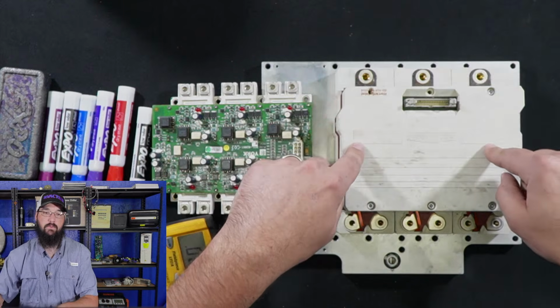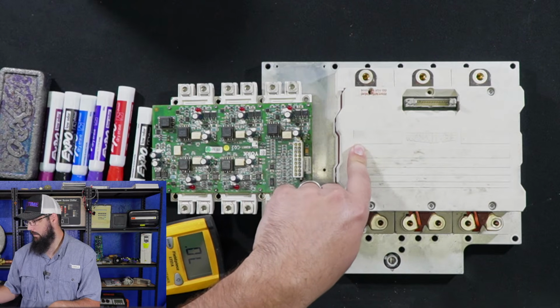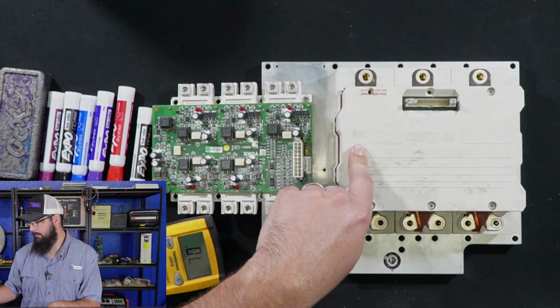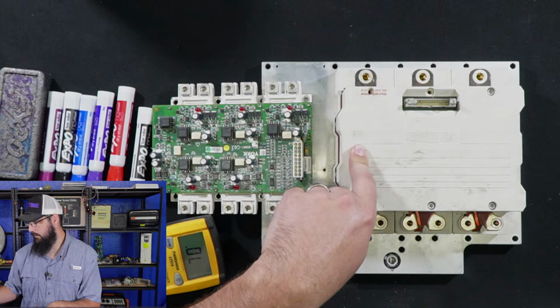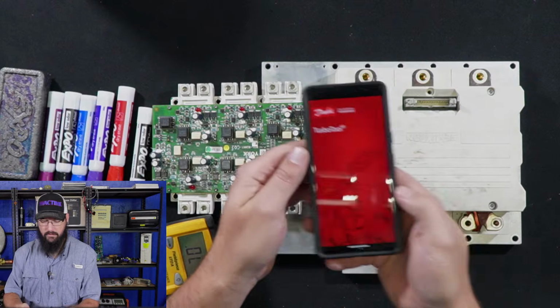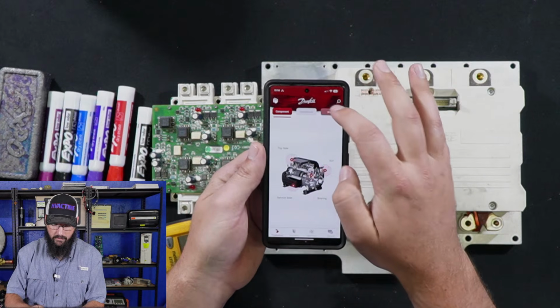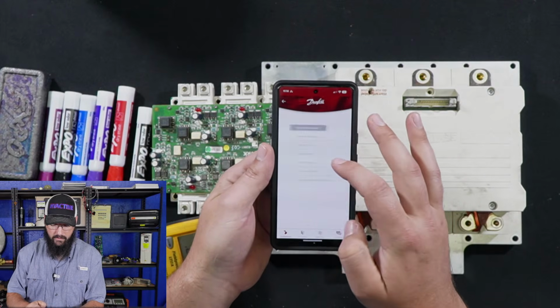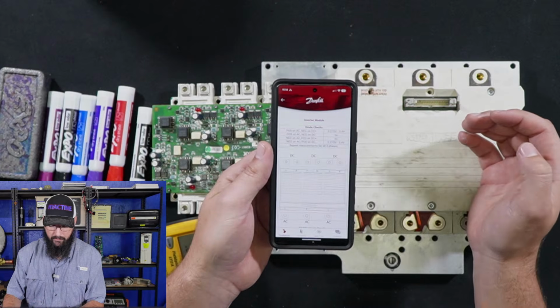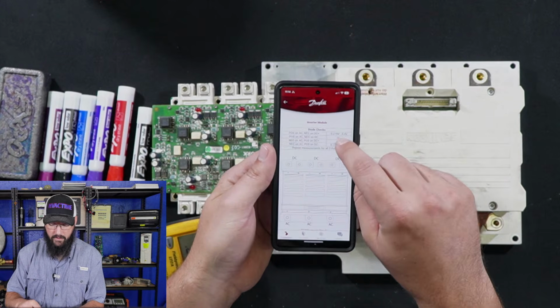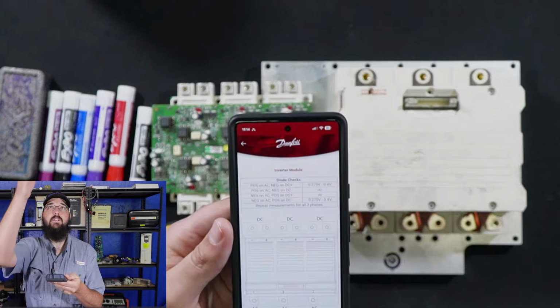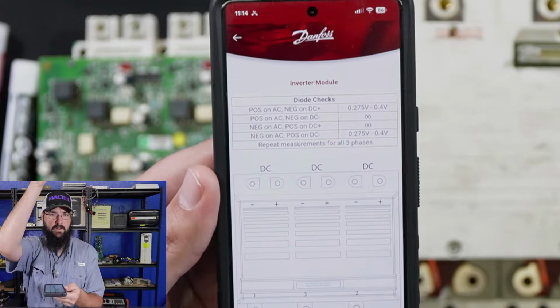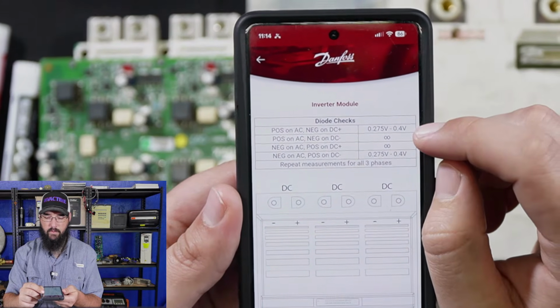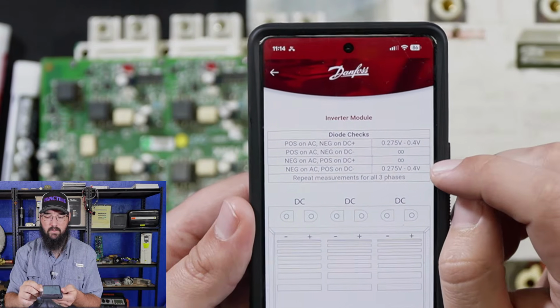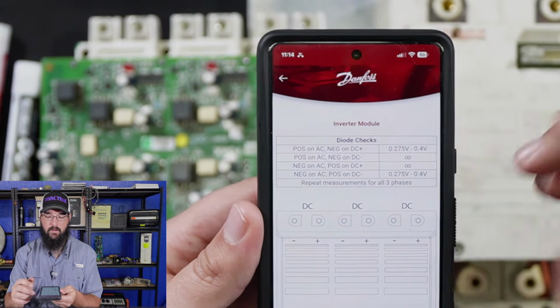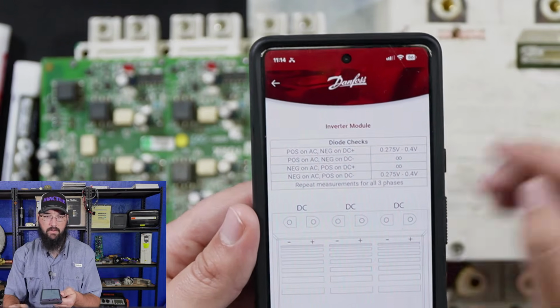So for this, we would use the Turbo Tool app, and I can show you that here real quick. Nope, that's the wrong one. All right, so here's Turbo Tool. Okay, so we can go to verify. We want to do a top side verify, and I want to verify inverter. All right, so here's my inverter values, and if you can zoom in on that. All right, so they want to see 0.275 to 0.4 when we get a reading, and they want to see OL on the other side. And you're going to do this per leg of this.